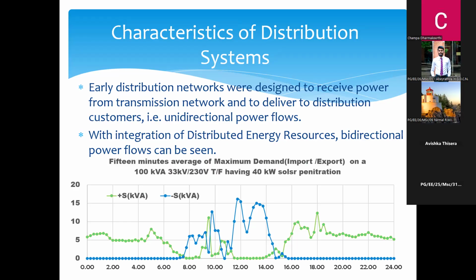This is an example of a transformer which has 40 kilowatt solar penetration in a village transformer. The values given here are kVA values, which are averaged over 15 minute intervals. The green color one is import, and the blue color one is export. If there is export in that particular 15 minute interval, it is shown in blue color.